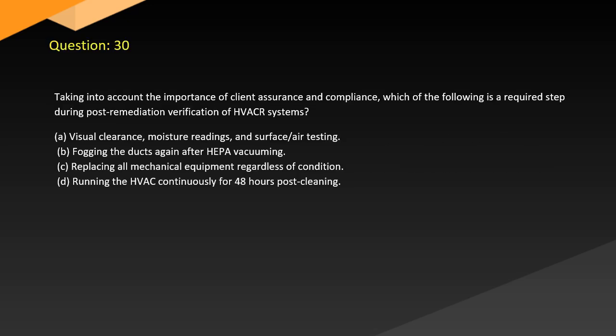Question 30. Taking into account the importance of client assurance and compliance, which of the following is a required step during post-remediation verification of HVAC systems? A. Visual clearance, moisture readings, and surface air testing. B. Fogging the duct again after HEPA vacuuming. C. Replacing all mechanical equipment regardless of condition. D. Running the HVAC continuously for 48 hours post-cleaning.